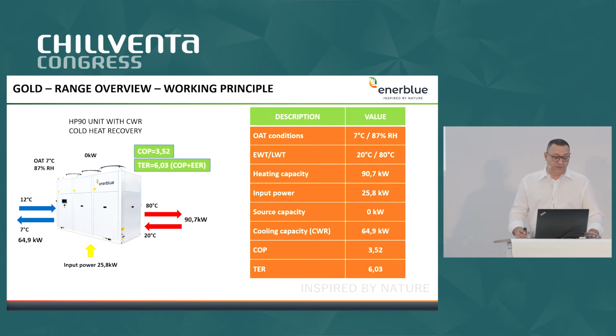So we are working like before with 20 inlet water temperature from the users and 80 outlet water temperature to the users, so more or less 91 kilowatt. The input power is more or less the same. In this case, fans are off, and we are working with the cold recovery, producing 7 degrees water with a capacity more or less of 65 kilowatt. In this way, we have a COP of 3.52 for heating, but the total energy efficiency ratio for the unit is about 6.03. It means that with 1 kilowatt of electric supply, we can produce more than 6 kilowatt in heating and cooling. And this could be very interesting for some specific application.